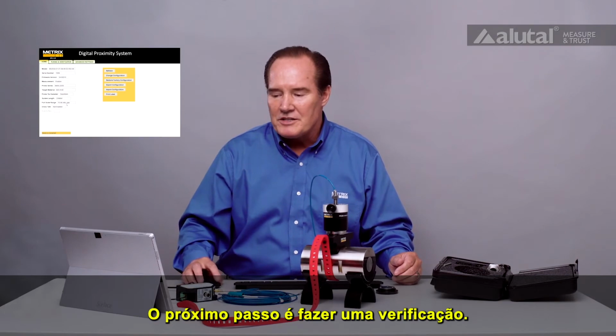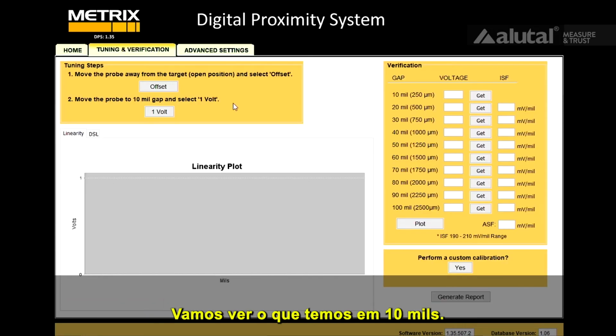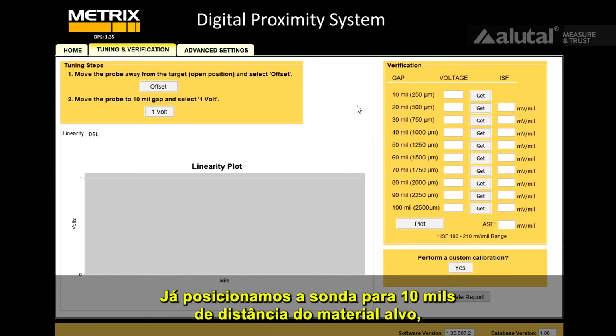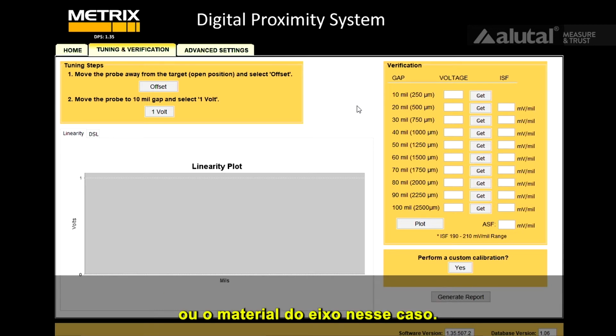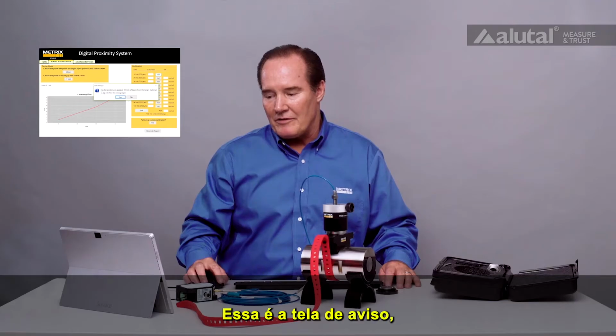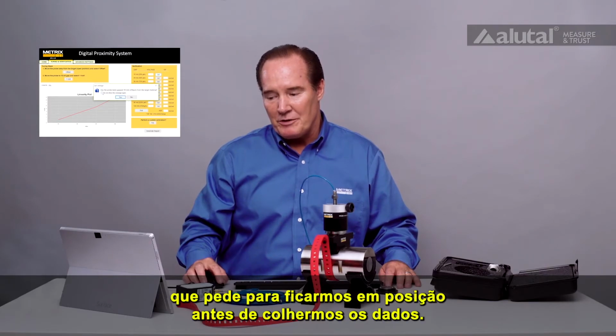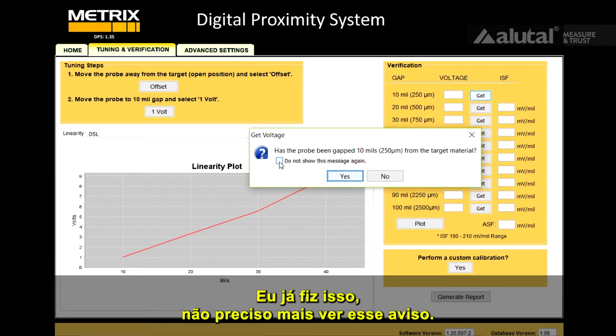So what we want to do next is a verification. We're going to see what we've got here at 10 mils, and we've already positioned the probe to be 10 mils away from the target material, or the shaft material in this case. So now we'll say get. Okay, we have the warning screen that says make sure you're in position before you take data, which I will, so I don't need to see this anymore.